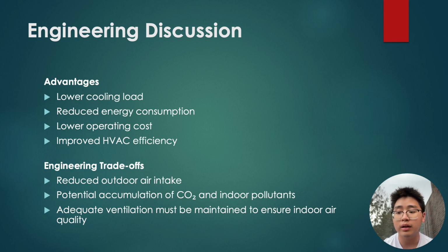Increasing the return air ratio also reduces the amount of fresh outdoor air entering the building. If the outdoor air supply becomes too low, carbon dioxide and other indoor contaminants may accumulate, reducing indoor air quality. Therefore, engineers must balance energy efficiency with adequate ventilation to ensure a healthy and comfortable indoor environment.